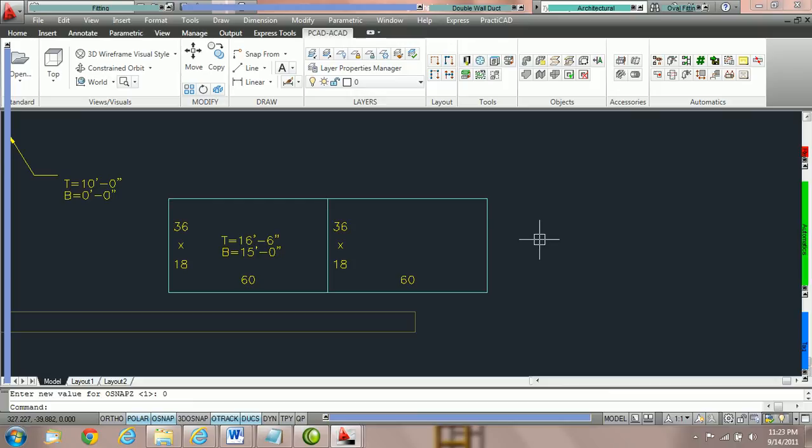When you're going to snap to a background, for example, follow the exercises on placing grills and snapping to a background. That'll show you a time where it's very good to have Replace Z on. However, if you're attaching duct to duct, especially in the isometric view, having Replace Z on will prevent you from attaching it at the right place. So it's important to understand when to use it and when not to use it. That'll conclude the tutorials on Replace Z.